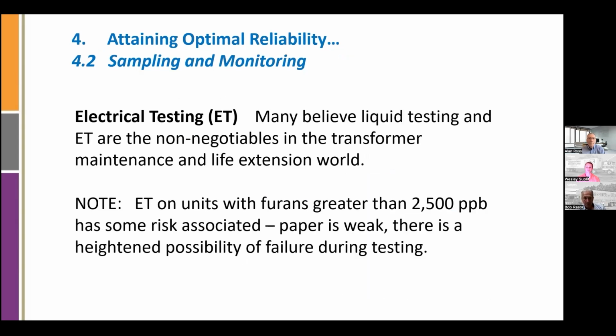Electrical testing. I'd point out, once the furans, if you're watching those, are over 2,500 parts per billion, there are some risks with testing. Not saying that it shouldn't be tested, because you may want to know, regardless of the condition of the insulation, if it can withstand a fault. But once the paper is weakened, and it truly is weakened, it could fail the transformer if the levels are too high in the furans.